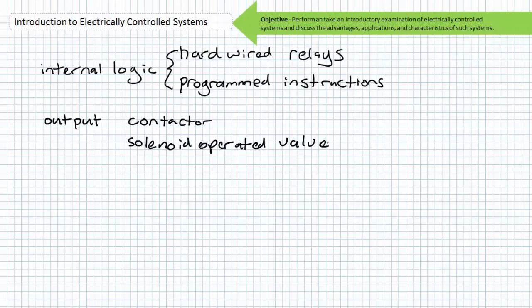We've already spent some time discussing two basic output devices: the coil of a contactor and the solenoid of a solenoid-operated directional control valve. A contactor turns on or off an electrical motor at the request of a low-voltage control signal. A solenoid-operated directional control valve shifts a fluid power valve when told to do so by a low-voltage control signal. These type of output devices form the principal point of interaction between the pilot and primary aspects of an electrically controlled system, and their function is to tell the primary device when to establish or interrupt service.